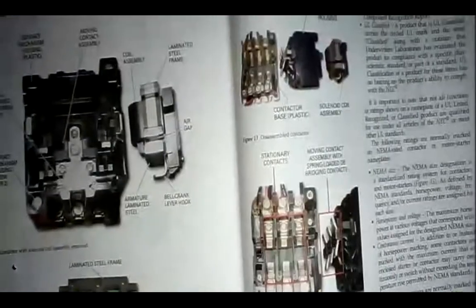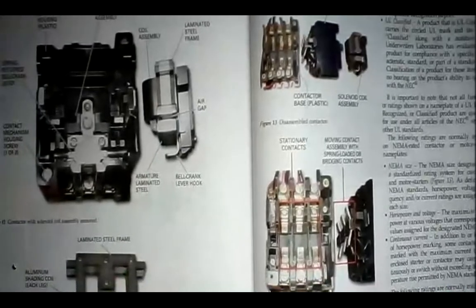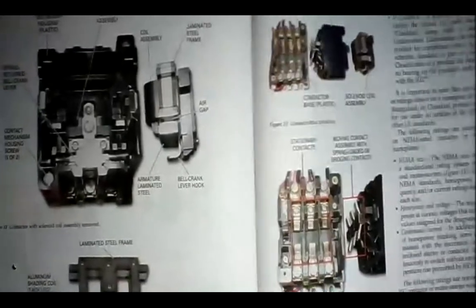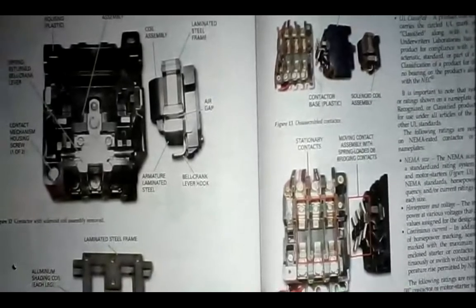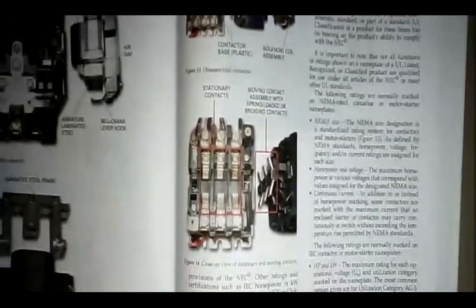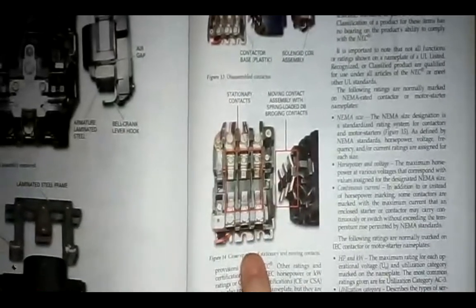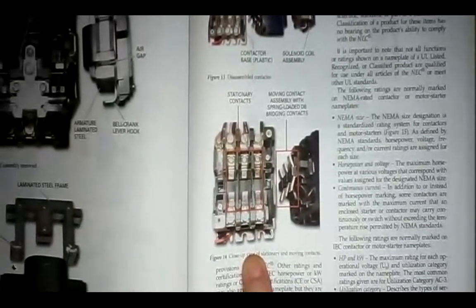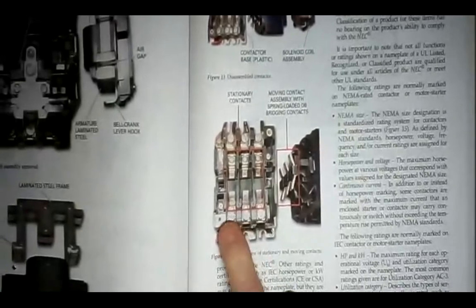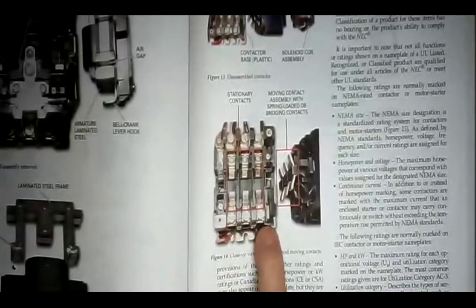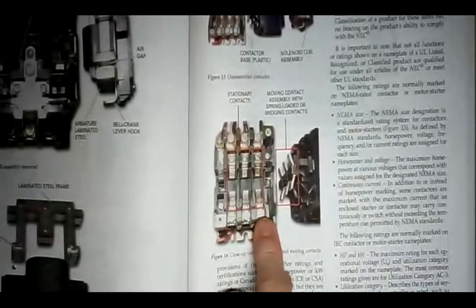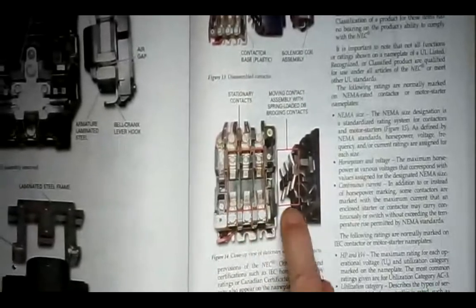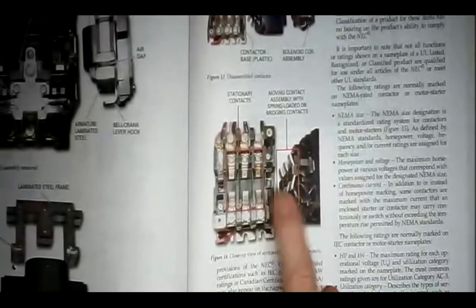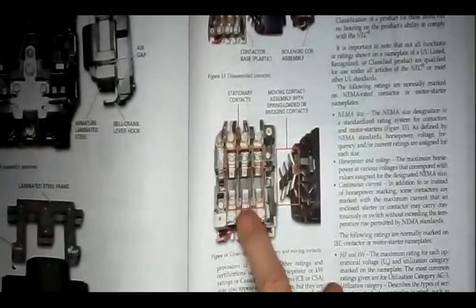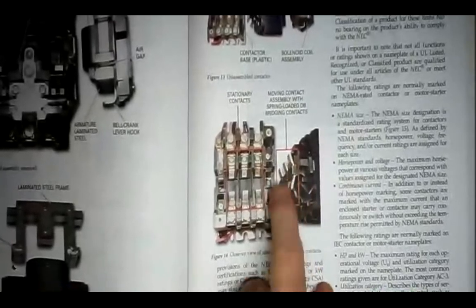Okay, and these are different types. I think this one is a Square D. We use a lot of GE. Here are the contacts internal, and you can see that they have the 3 poles for the 3 phases, A, B, and C. And these are the contacts, the movable contacts, that make contact with these stationary contacts. These will come down on top and seal in.